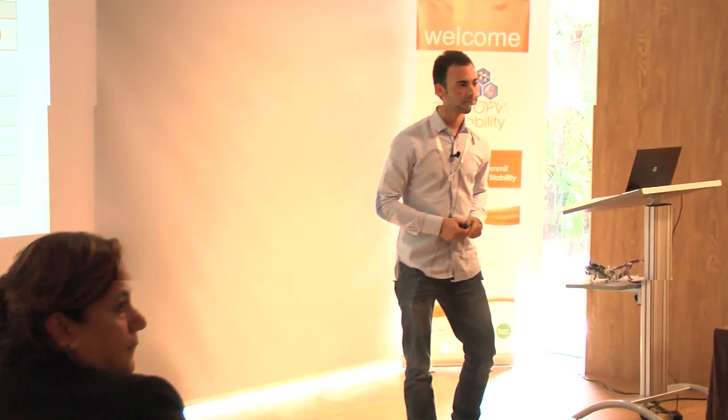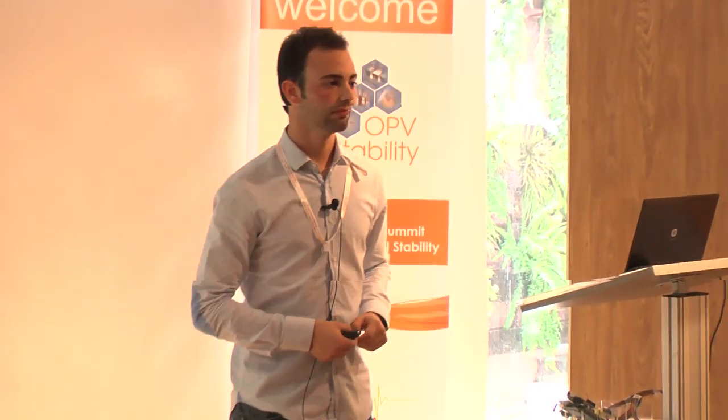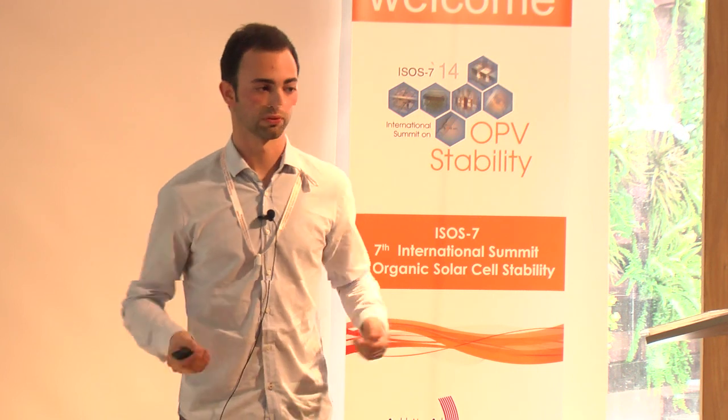If all of us measured with the same equipment, maybe it's a good idea to do, I don't know, you call it round robin or not, to measure it outdoor at different locations. And in this way, we will really see the effect of atmosphere, temperature, light spectrum, intensity, whatever. This can be very accurate. Maybe it's not round robin, but it can be a good inter-laboratory study. I think the possibilities are a lot. We have to decide. Soren, did you have a question?